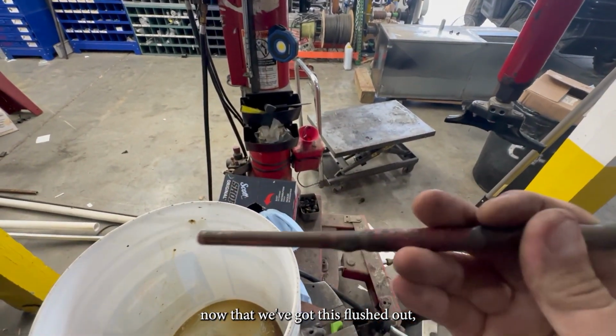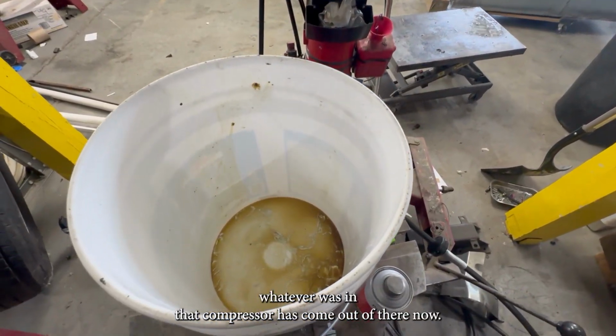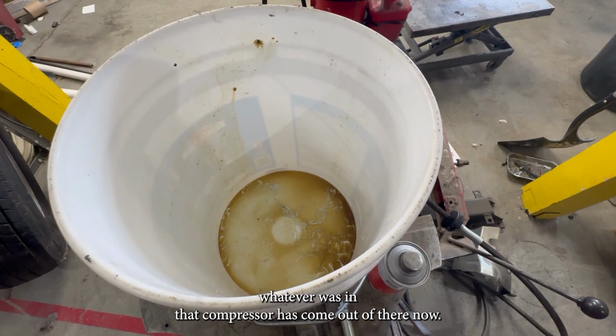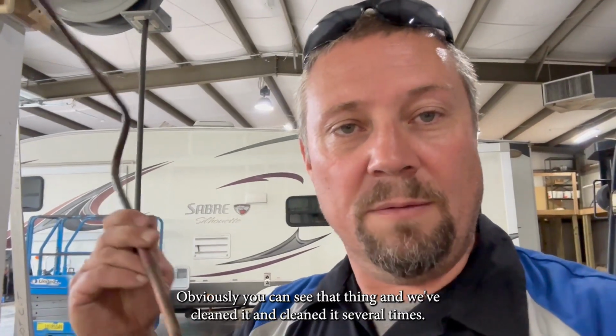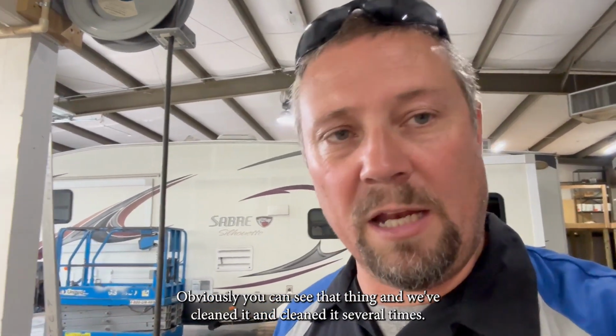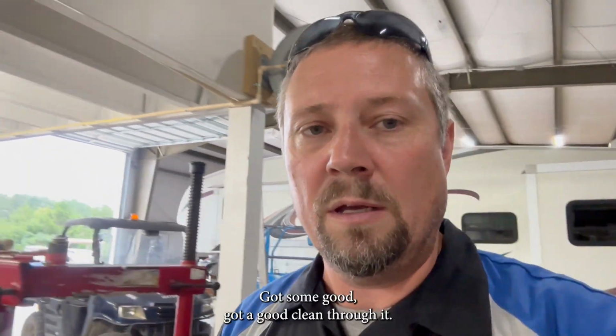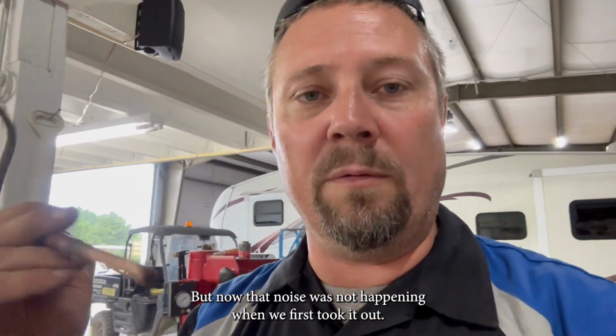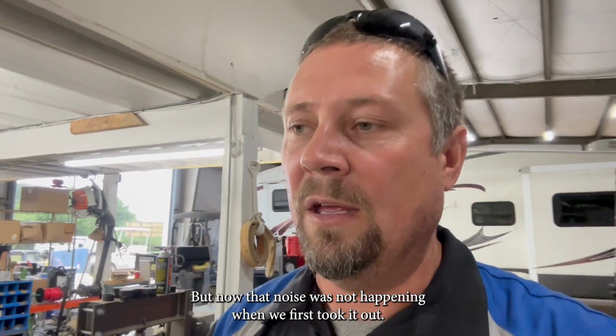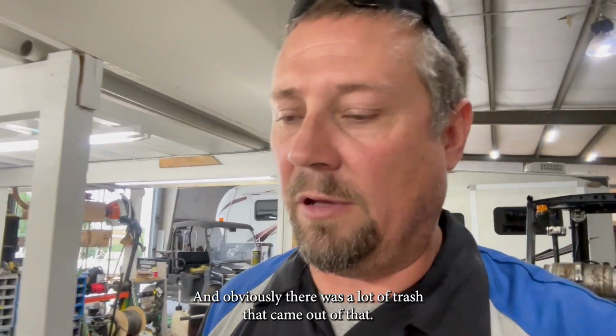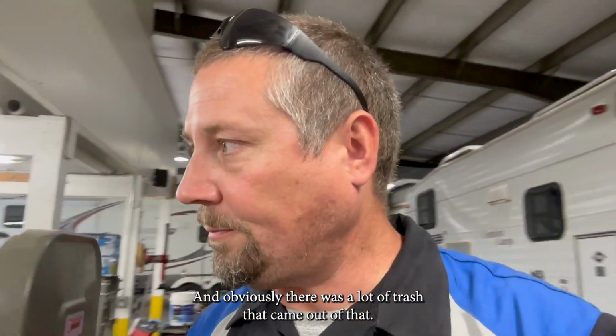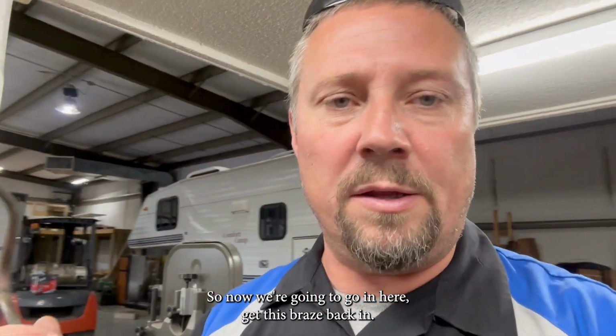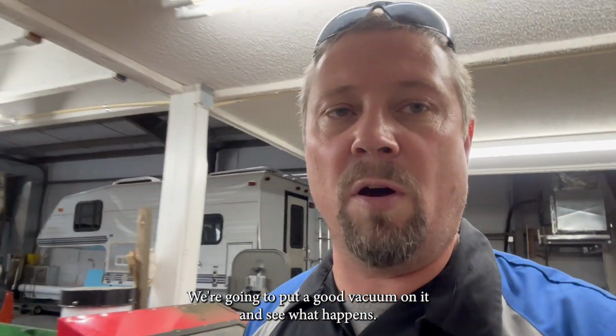Now listen, now that we've got this flushed out, whatever was in that compressor has come out of there. Well, obviously you can see that, and we've cleaned it several times, got a good clean through it. But that noise wasn't happening when we first took it out, and obviously there was a lot of trash that came out of that. So now we're going to get this brazed back in, pull a good vacuum on it, and see what happens.